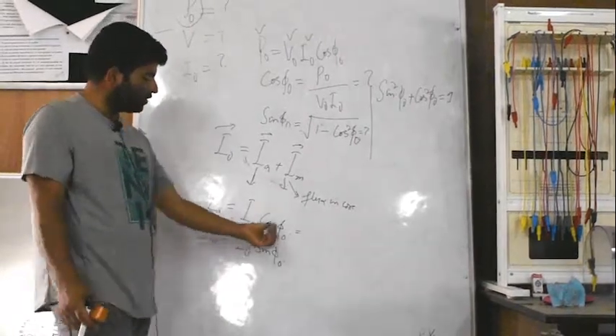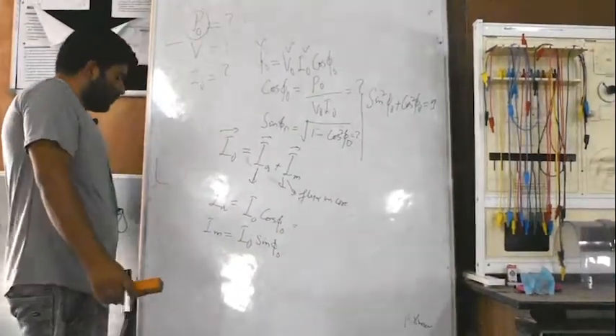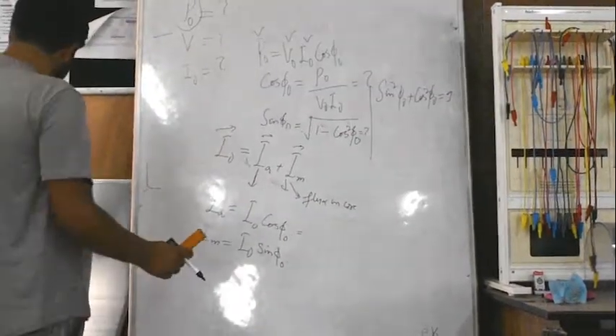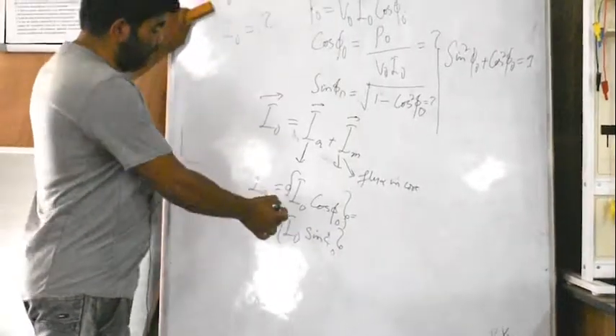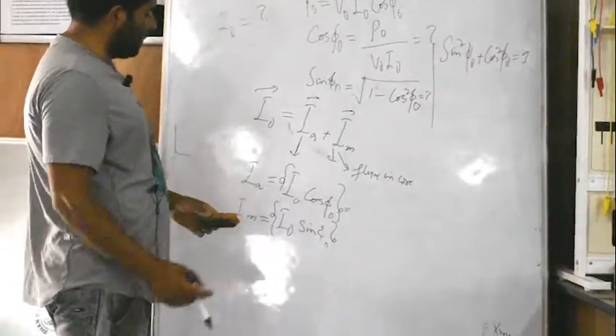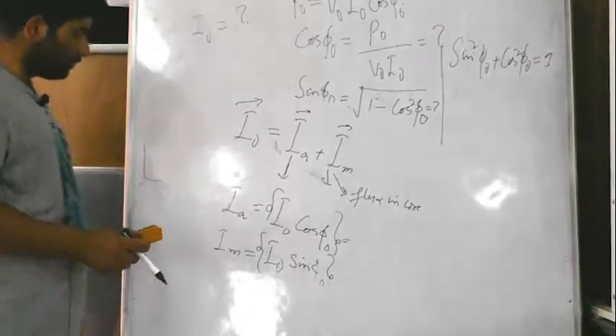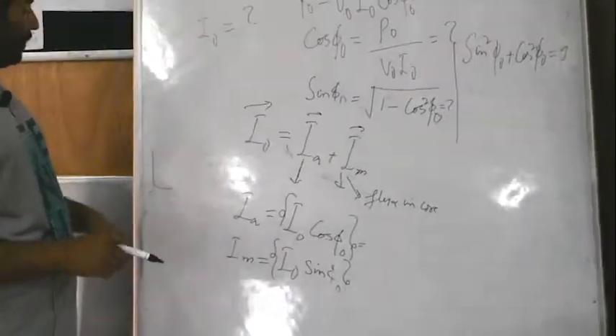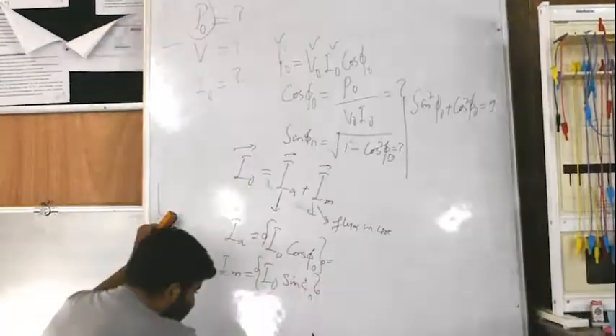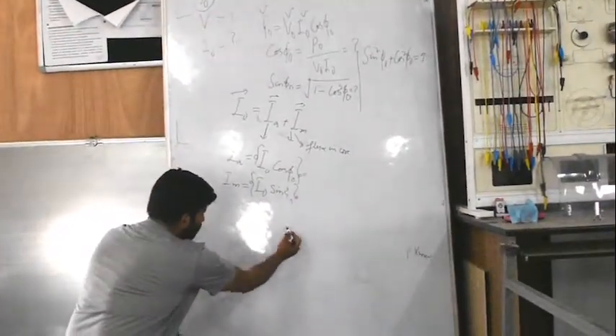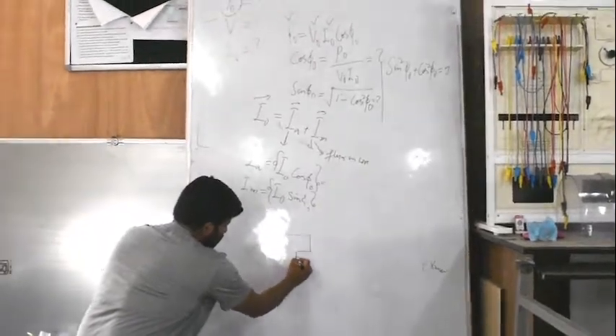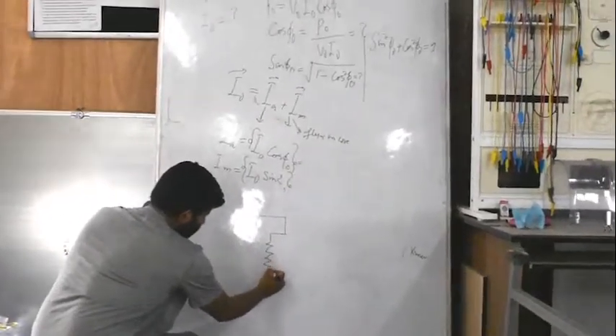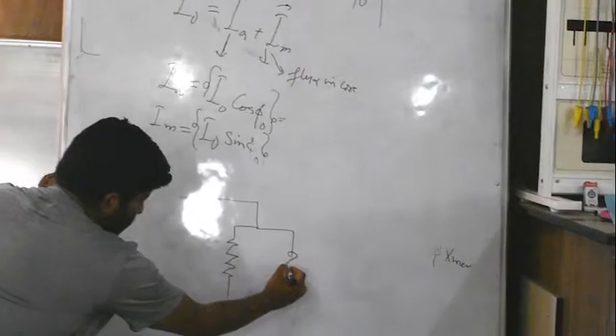By taking the products I naught cos phi naught and I naught sin phi naught, you can calculate the active and magnetizing components. So, knowing these two components of no load current, Ia and Im, you will be able to frame the no load equivalent circuit by obtaining the shunt branch parameters with this procedure, because at no load we have the equivalent circuit like this.